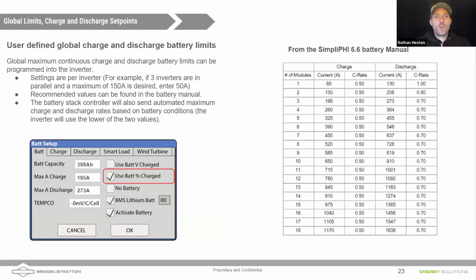So let's start off by talking about charge limits for batteries. I'm going to specifically point out, with a communicating battery, the battery capacity is going to come in, and the max charge and discharge limits that the battery is capable of will automatically appear. What we are looking at on this screen, though, is user-defined maximum global charge and discharge limits. So what do I mean by that?